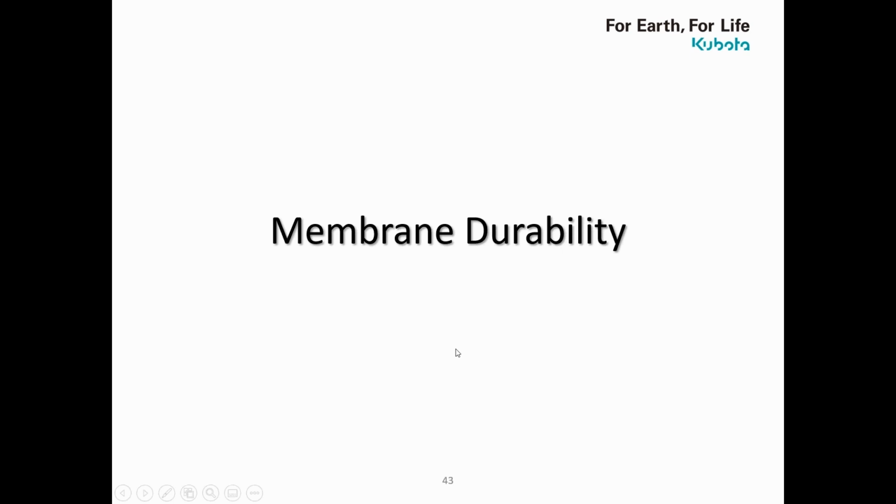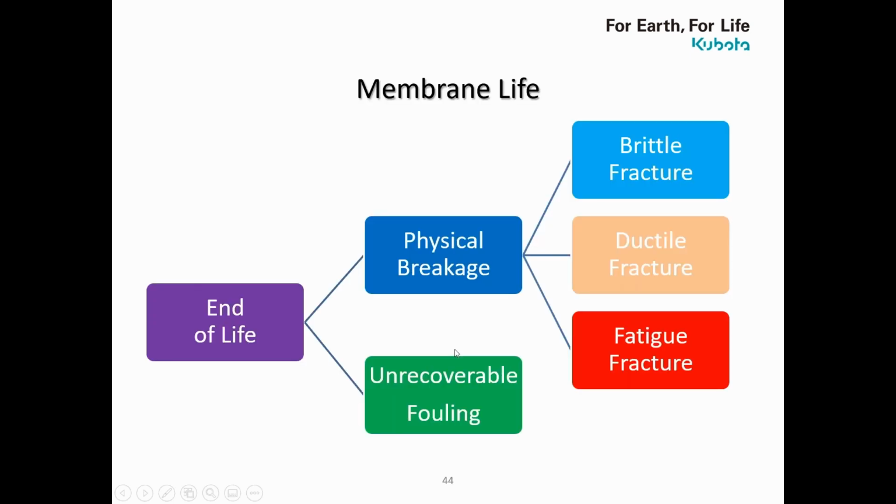The membrane lifetime and durability. At the very end of the lifetime, we will typically have a physical breakage of the sheet and the plate itself, but there is a lifetime on the membrane. I haven't really seen much unrecoverable fouling happen. A lot of foulings are recoverable. It's more of a physical breakage at the very end of the lifetime.